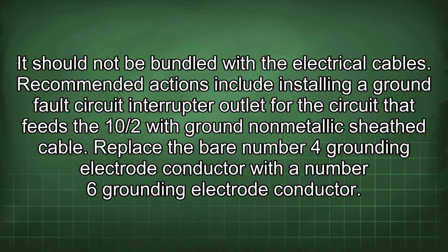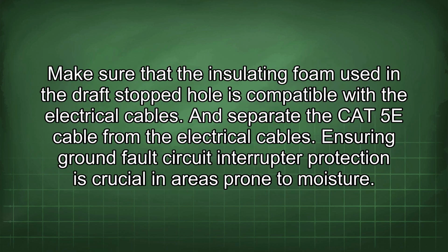Recommended actions include installing a ground fault circuit interrupter outlet for the circuit that feeds the 10/2 with ground non-metallic sheath cable. Replace the bare number 4 grounding electrode conductor with a number 6 grounding electrode conductor. Make sure that the insulating foam used in the draft-stopped hole is compatible with the electrical cables, and separate the CAT 5E cable from the electrical cables.